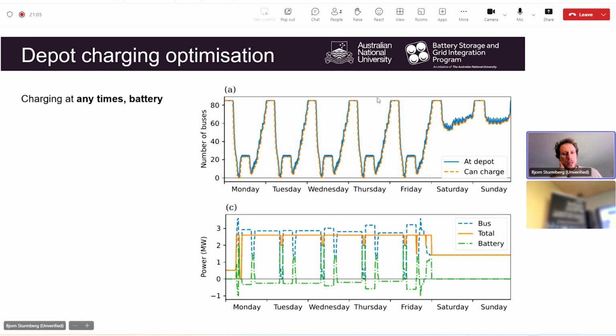Then if you introduce a battery into the depot, the only thing that's changed is in the bottom graph, the peak power loads, the orange load of the bus fleet plus the depot. That's been brought down a little bit, by about a quarter of a megawatt. You can see the battery is charging mostly at those moments where the buses are all on the road, so the demand becomes really constant across the weekdays.